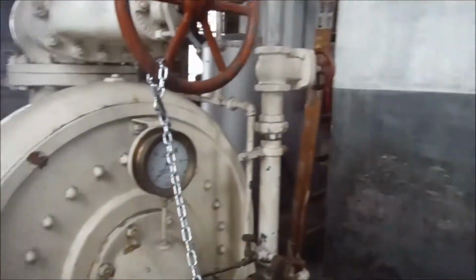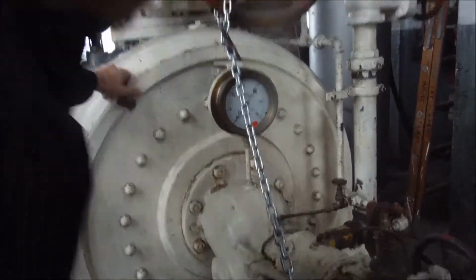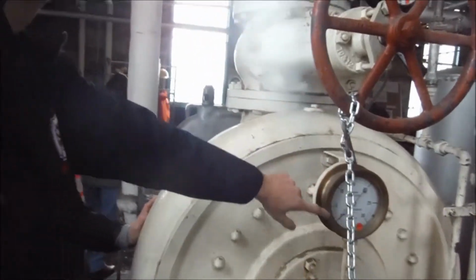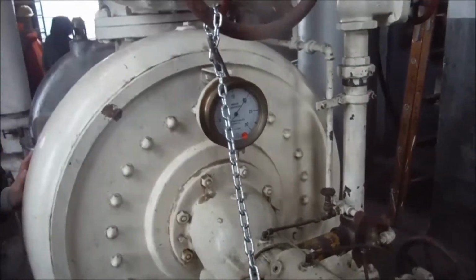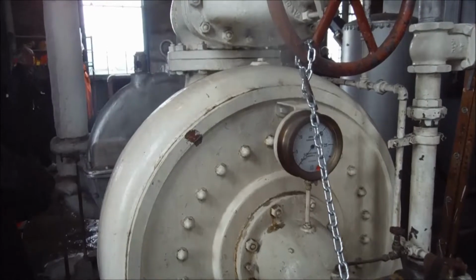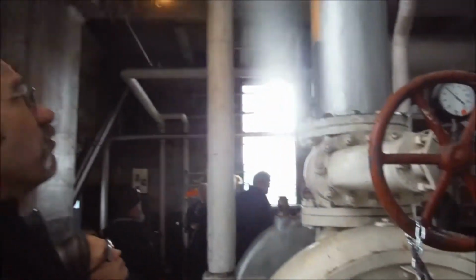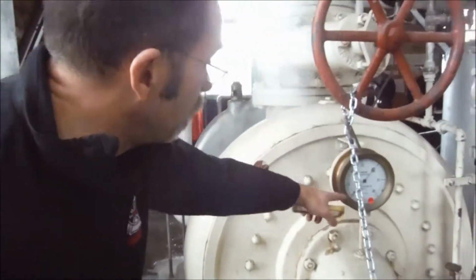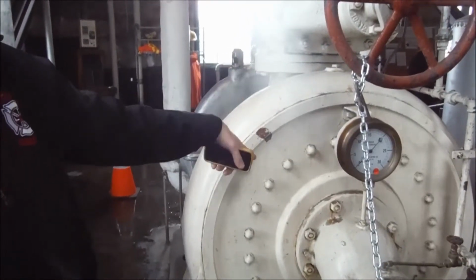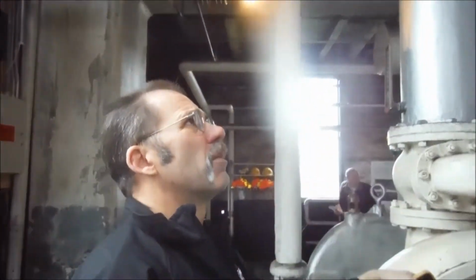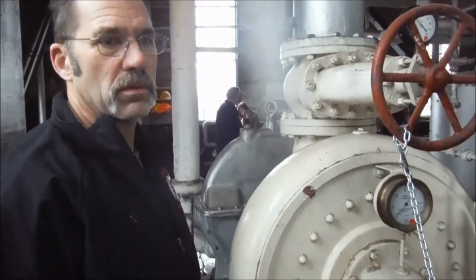We've got something out of the bottom of the casing, something into the middle of the casing. It's a vacuum gauge, so it must be a pump to the condenser. There's a lot of work done to remove air and non-condensable gases from the condenser, because you're always getting air into your system and there's gases that won't condense, and what you want in there is pure steam condensing to pure H2O. So being as we're dealing with what's essentially a turbine-driven vacuum pump, quite possibly it's doing the same thing that piston pump did over there, which is removing air and non-condensable gases. So basically we're looking at a steam-powered vacuum pump. Yeah.